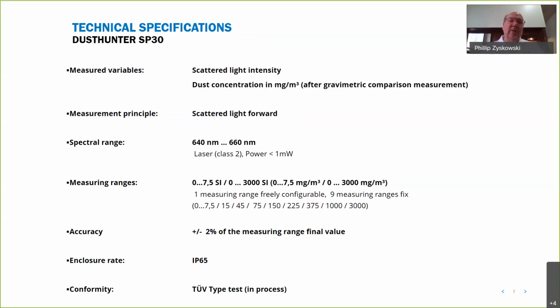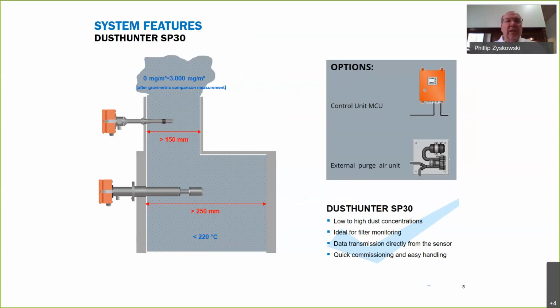Accuracy is right up there, what you would expect from a scattered light device. And then the packaging and the testing is, again, everything you would expect. So essentially, we've got 2 models depending on the length that need to go into the ductwork or the stack. And optionally, and this is what goes into that claim that I've made about it being inexpensive, you do not need a control unit. Everything that you see on the left side here is standalone. And so you don't need an extra device to get your output or your digital input. And so that's a way we can make the unit less expensive. Also, we do have an optional purge air unit. So this, as it comes out of the box, for most applications, the purge air is not required, but it is an optional feature.